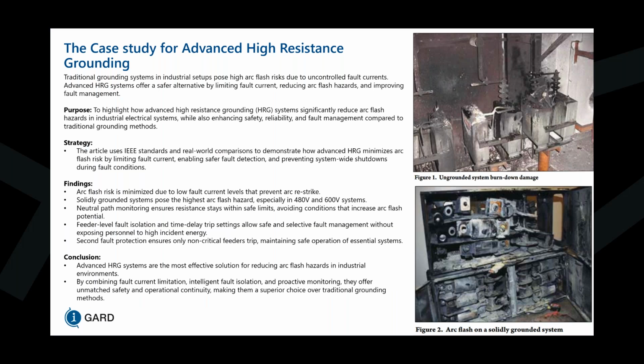We're using our arc flash relay as well to pick up on arc flash via fiber optic cables and pressure. The high resistance grounding system is employed at the source between neutral and ground to lower fault current levels and prevent arc restrike. As you know, solidly grounded systems pose the highest arc flash hazard, especially in 480 volt and 600 volt systems. Neutral path monitoring ensures that the resistor is there to do its job when a phase to ground fault occurs. So we're monitoring for both open circuit and short circuit conditions.